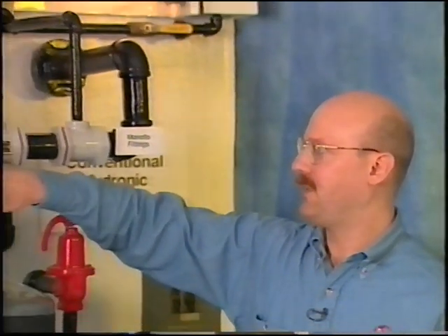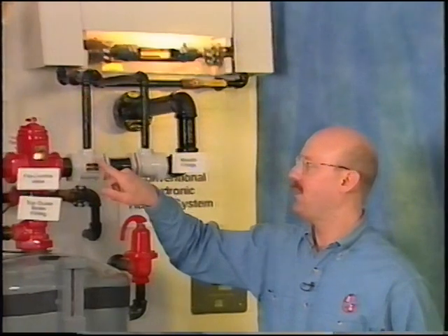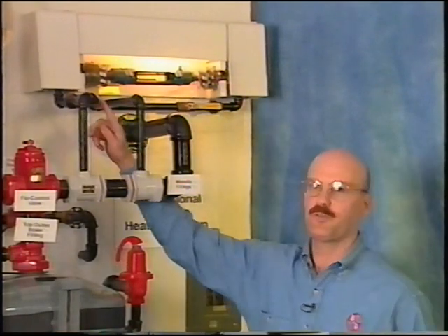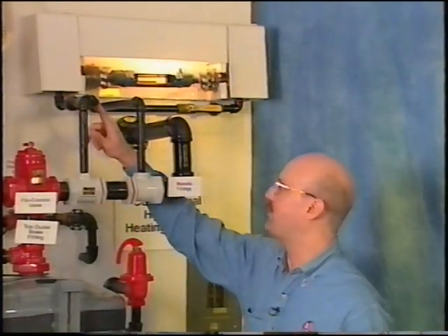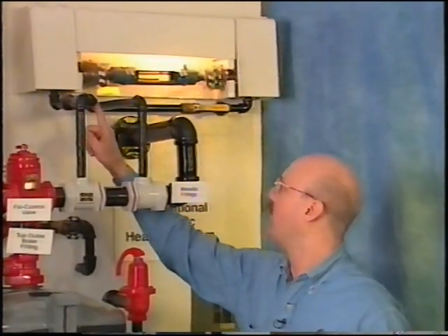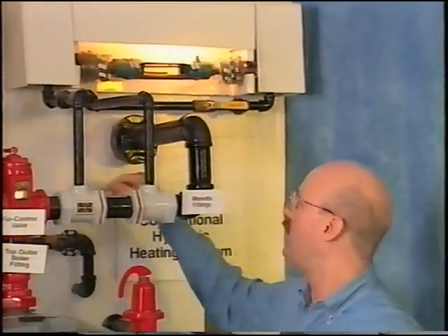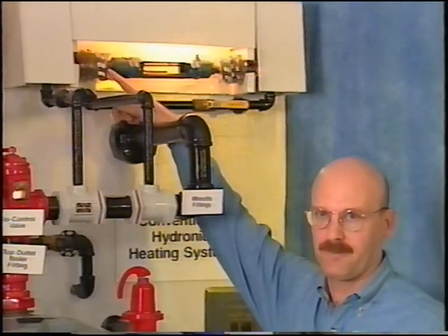Next, the water will circulate through the system. As it's circulating through the system, the water will be allowed to cool down. As the water cools down, air will come out of solution, and this will cause noise problems. Also, because air is coming out of solution, soon it's going to hit a part of the system where there is a low velocity. Most likely, that will be the radiator.